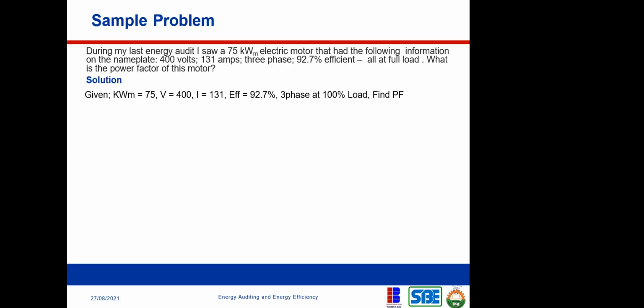Let us do a simple sample problem. During my last energy audit, I saw a 75 kilowatts mechanical electric motor that had the following information on the nameplate: 400 volts, 131 amperes, that is the current, and it's a three-phase motor. I'm told that it is 92.7% efficient at full load, meaning the load factor is 1. So what is the power factor of this motor?